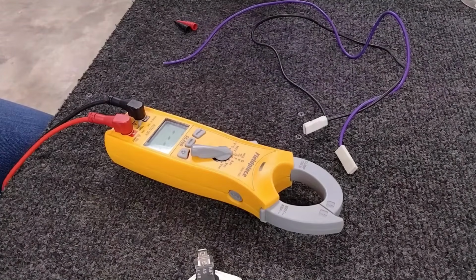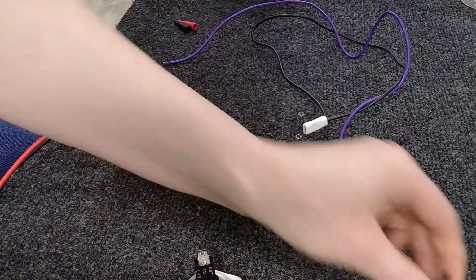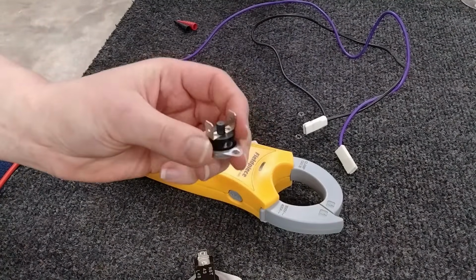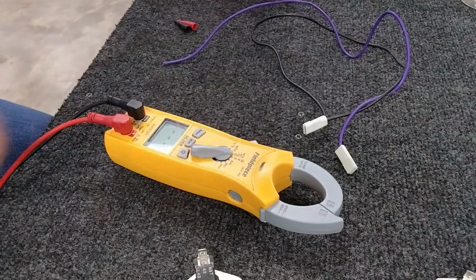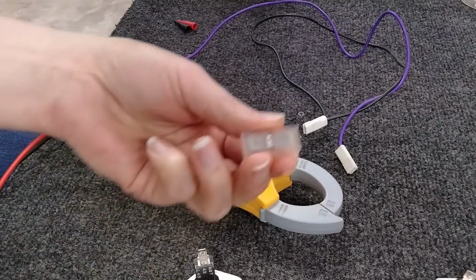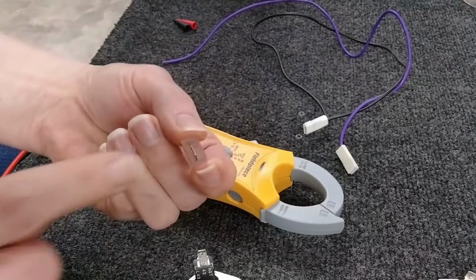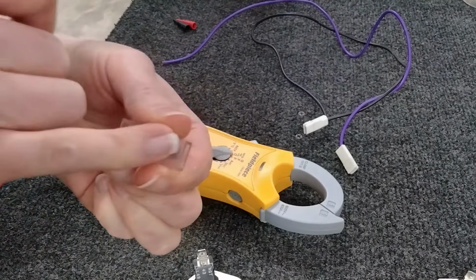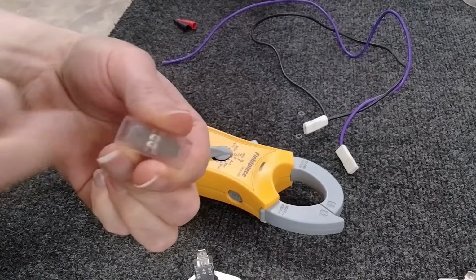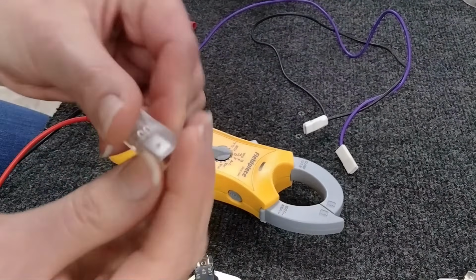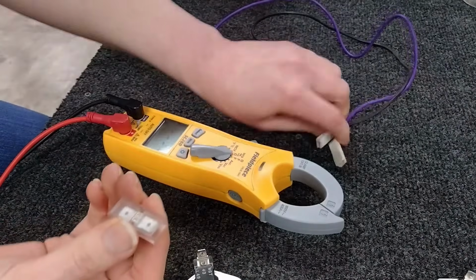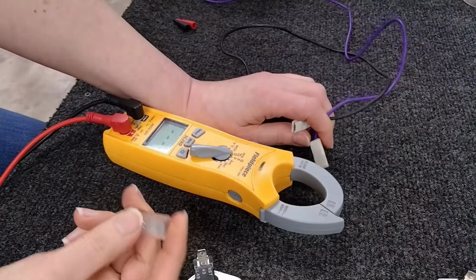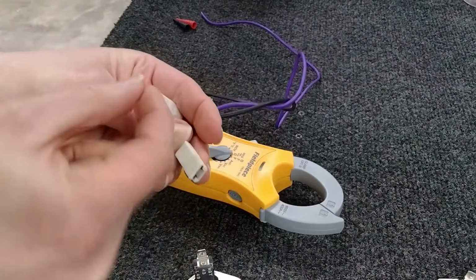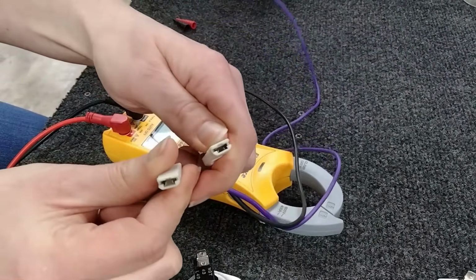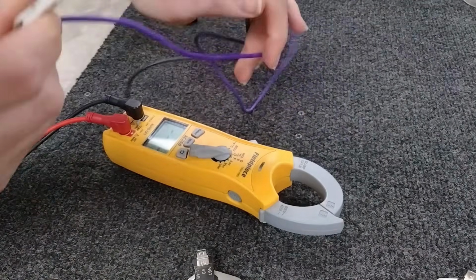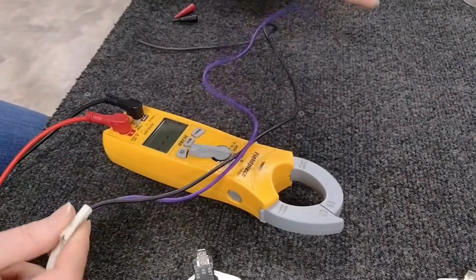And this doesn't work for all limits. We'll get to this special guy, your rollout switch, in a minute and answer a few questions about why this is different. But for now, if you don't have this little handy jumper like I do, which has a double-sided male connection with a joined metal piece in the center, fantastic. If you don't have these, you can put a jumper here, maybe some gator clips between your female quick connects, and figure out if that limit is the culprit.